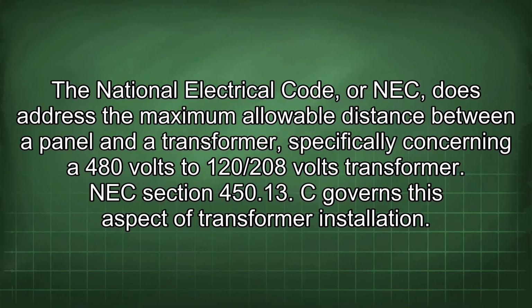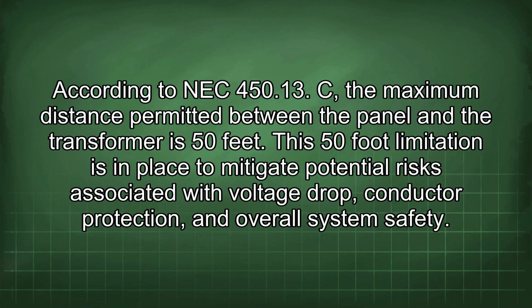The National Electrical Code, or NEC, does address the maximum allowable distance between a panel and a transformer, specifically concerning a 480 volts to 120/208 volts transformer. NEC Section 450.13 C governs this aspect of transformer installation. According to NEC 450.13 C, the maximum distance permitted between the panel and the transformer is 50 feet.